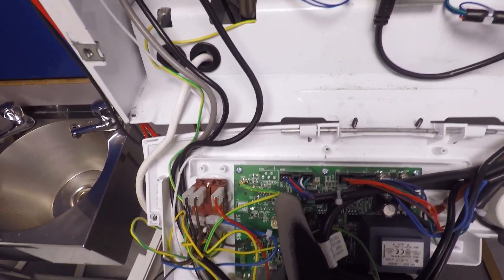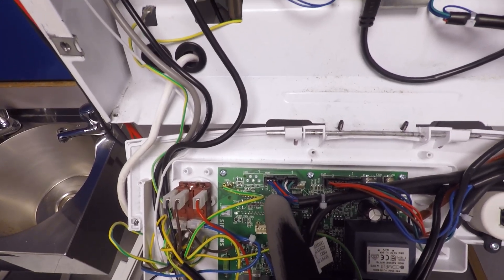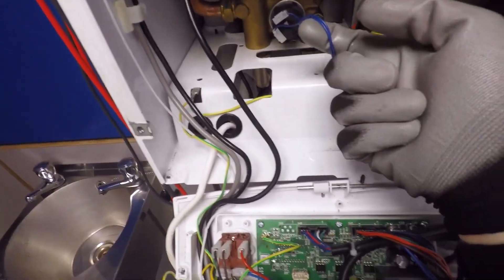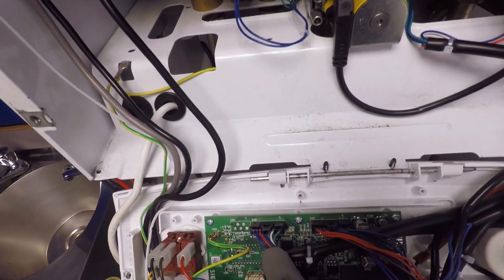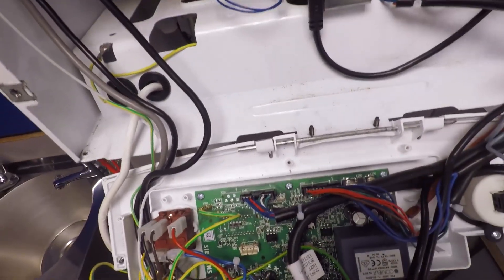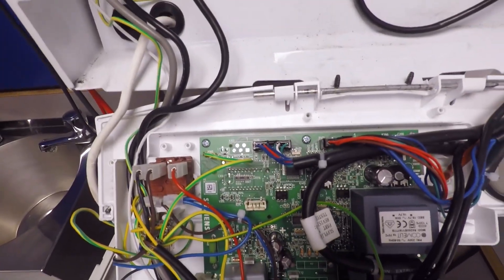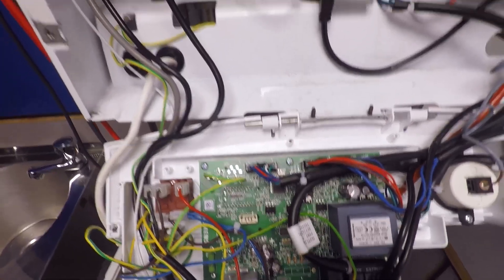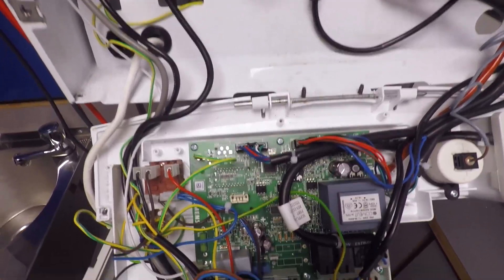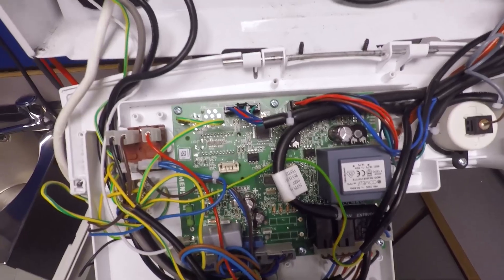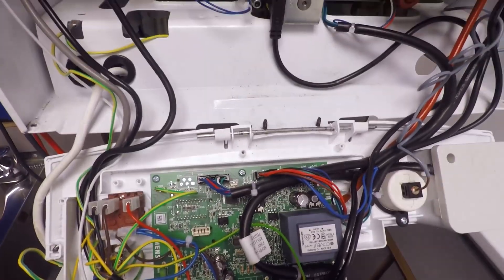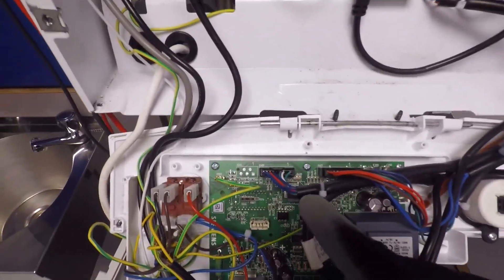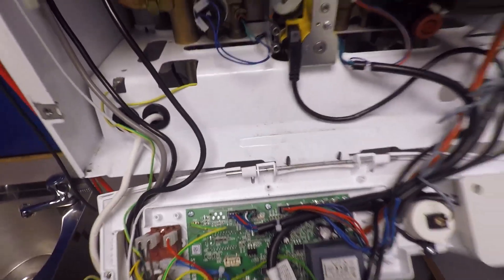We're not bothered about the first two blue wires because those are for the low water pressure switch. So we're looking at the red, the blue next to that and the white towards the end there. But keep it really simple. The way I used to remember it is running water, R and W. So red and white. When I'm running water, I should have voltage between the red and the white wires.